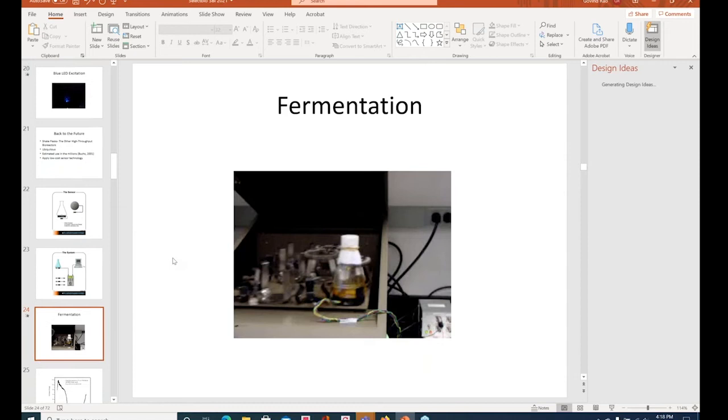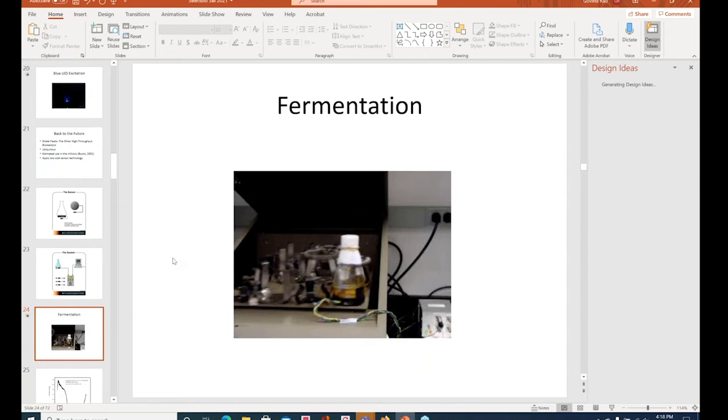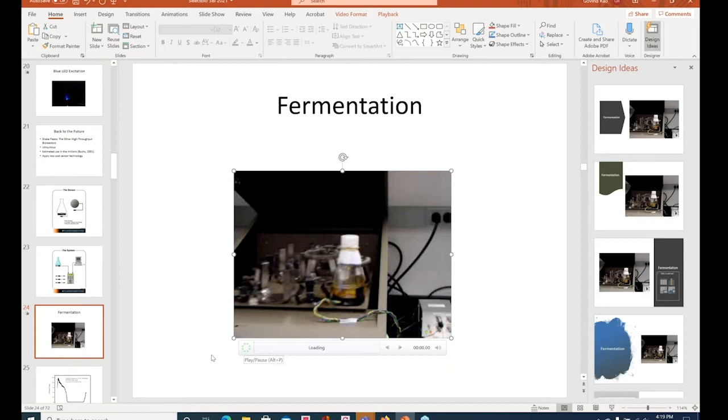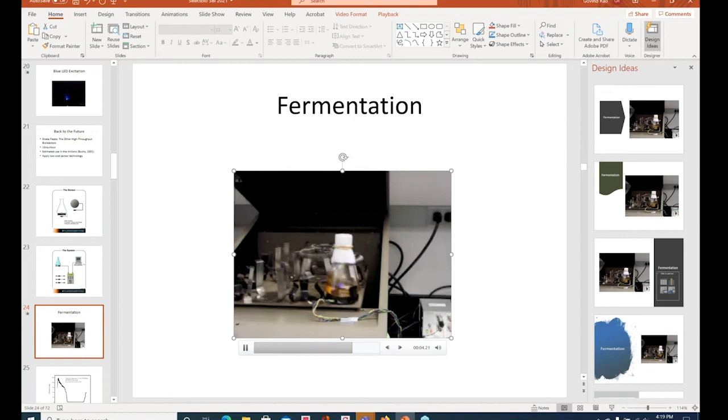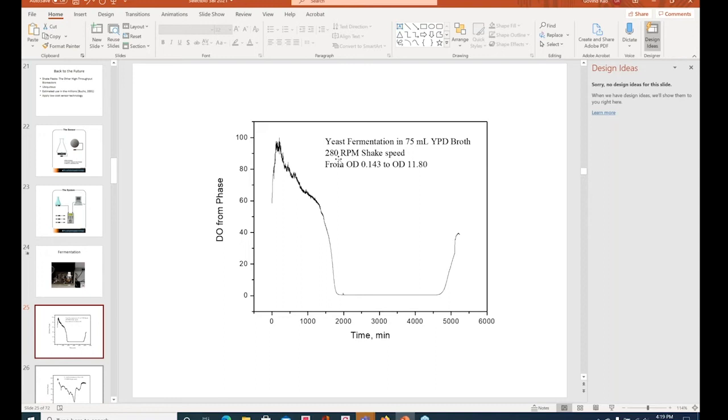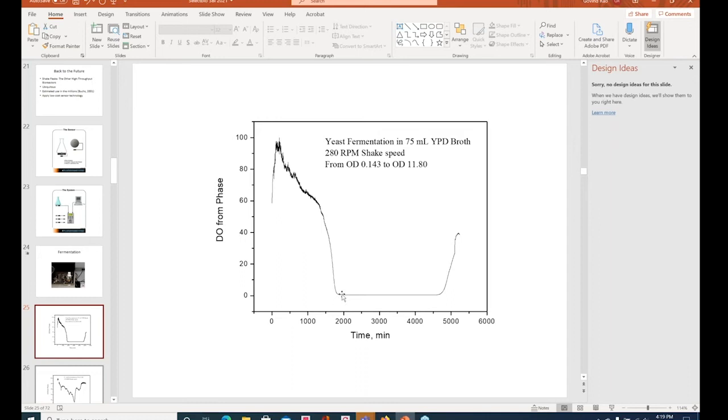So this again is a historical video. This is the very first shake flask fermentation in the lab that was being monitored. So it was hooked up to this prototype device and we have the piece of tape holding the cable because one of our big concerns was that the cable would work itself loose. We set up the experiment with a yeast fermentation at 280 RPM. We didn't know what to expect. This shake flask, everyone said, I don't know why you're bothering because these things are vigorously agitated. So there's no issue with oxygen. That's really a waste of time. Don't bother. So I was like, I got to try it anyway. It's so cool. So we started the experiment and my God, my heart sank after about the 2000 minute mark, because it started reading zero. So I was like, crap, some wires got disconnected.